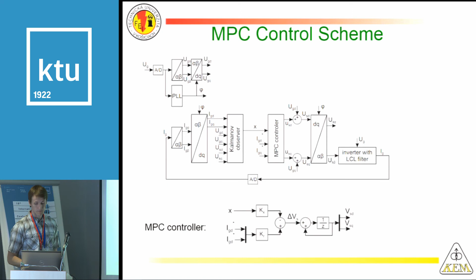Look at that Kalman observer. I think you are familiar with it. I have some dynamical process and then a Kalman observer, which can do two things. First, it can improve the information from a sensor, since there is always some noise, so I can remove that noise using the sensor equations. Second, I can predict or observe the system state if I'm missing some system variables. In my case, I had only one measured system variable, and the remaining two, the inverter side current and capacitor voltage, were observed by the Kalman observer.